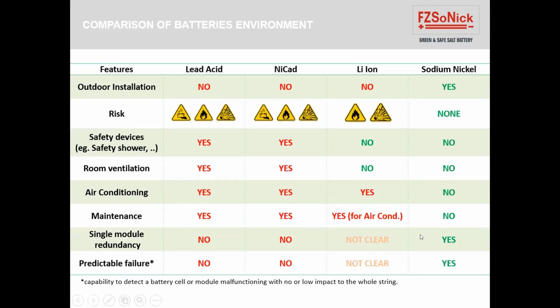As I mentioned, we have a BMS that is able to detect if anything is not correct inside the battery - for example, a failure of one cell. Typically, a failure of one cell doesn't affect operation of the battery, because the failure mode of our cell is a short circuit. As the cells are connected in strings, losing a cell means the string is still available - it has a little bit lower voltage, but the string is completely available.